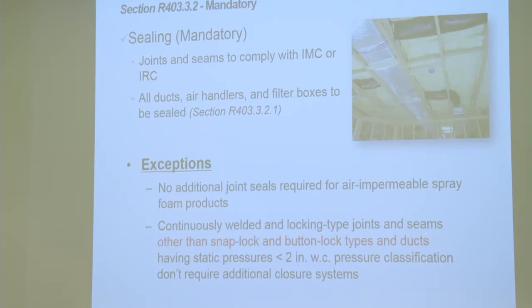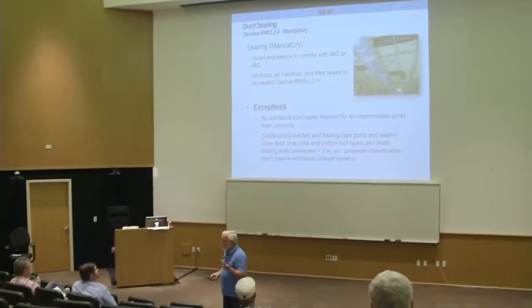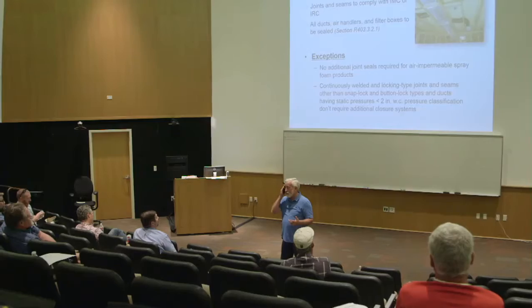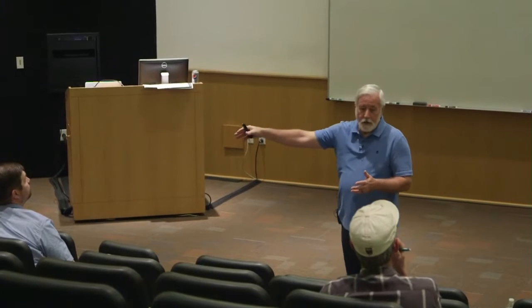Sealing, and this one's going to change. Basically, it doesn't matter where the duct is, it has to be sealed. If it's in the attic, you should really make sure that duct is tight, because not only does heat transfer like he mentioned, if we leak 100 CFM out in the attic, guess what? That's like an exhaust fan throwing 100 CFM away, and we just barely spent the money to heat or cool the air. Or if our return's leaking, we're sucking 140 or 150 degree air into our system. So it's really important that those are sealed.